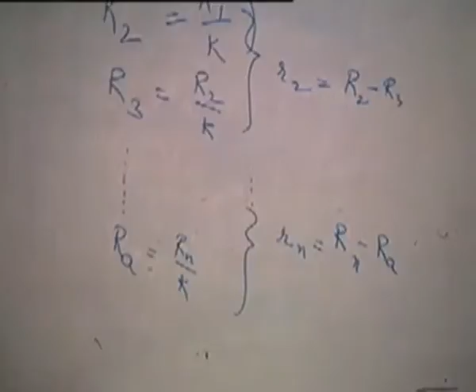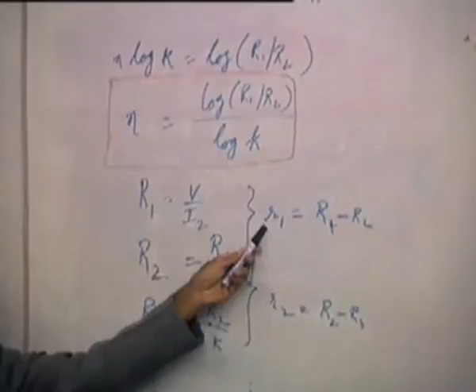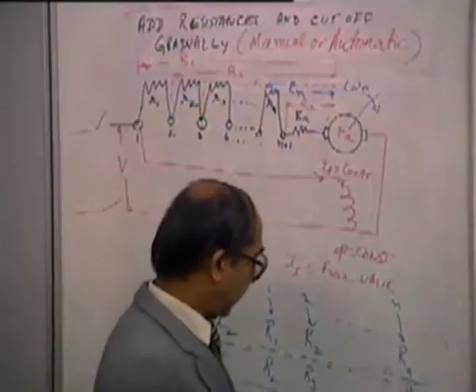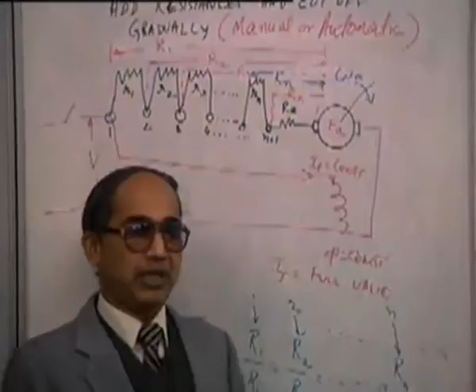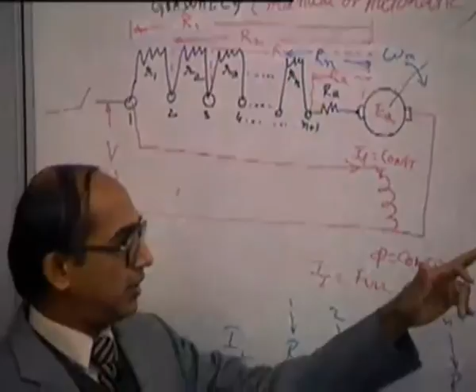So you will find from this logic, so long as you know the ratio of maximum to minimum current permissible, that is K, you can find the number of studs and also find out the value of the resistance elements R1, R2, R3 and so on up to Rn. So all these resistance elements can be determined from this. This is an important factor from which one can decide the number of steps and the number of resistance elements as well as their values. So this is the basic principle of an n element DC motor starter.